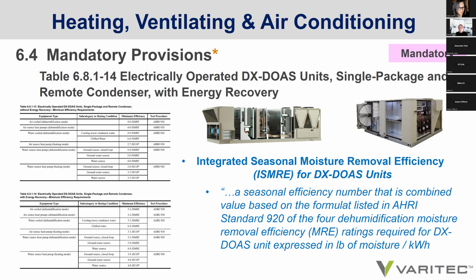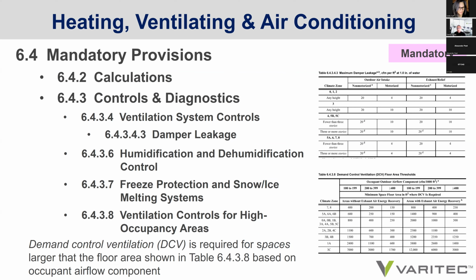Be aware that in the 2019 90.1 standard, language was added regarding DX DOAS units, 100% outside air units. A new metric was added. It's called ISMRE, Integrated Seasonal Moisture Removal Efficiency. So a DX-DOAS will have to comply with the minimum ratings for dehumidification. And those values are listed on table 6.8.1-13. So that is certainly the language since 2019, which would imply that the city of Scottsdale that has adopted the IECC 2021 code will need to look at integrated seasonal moisture removal efficiencies for DX-DOAS units that might be applied in their projects, depending on what their authority having jurisdiction says regarding a building's design mechanical system.